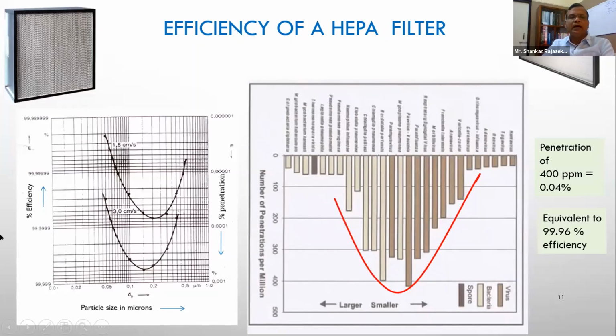So as we look at this, the curve is again very similar to this, and they have given it in ppm, parts per million, as the penetration. So a penetration of 400 ppm is 0.04%, which means it is 99.96% efficiency. So this bottom point I'm talking about, this 400, more or less matches with the engineering calculations that we get.